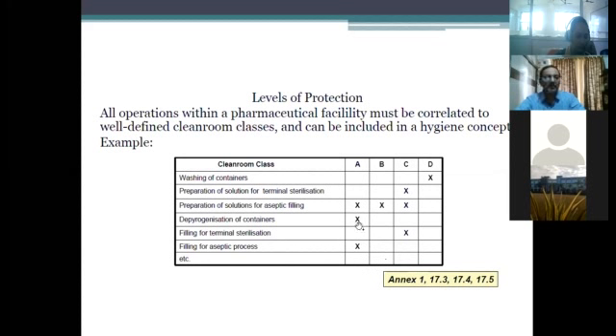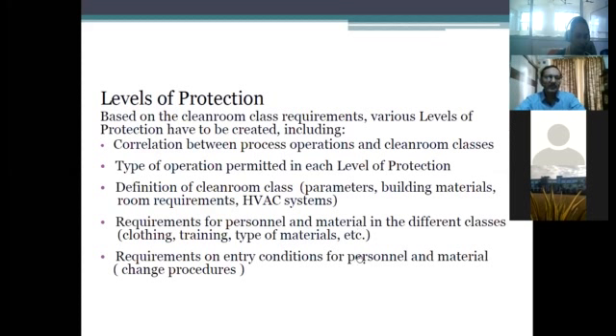So that is how we talk about levels of protection. Based on the clean room class requirements, various levels of protection have to be created. There is a correlation between process operations and clean room classes, the type of operation permitted at each level of protection, the definition of the clean room class, and parameters like building materials, room requirements, and the HVAC system.